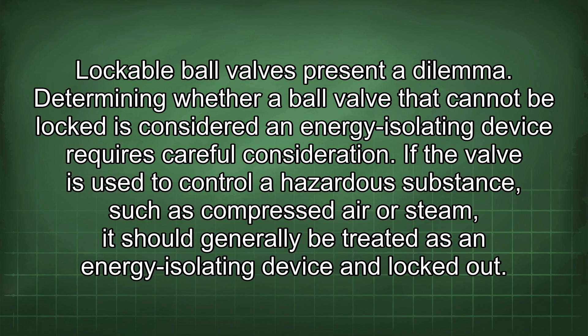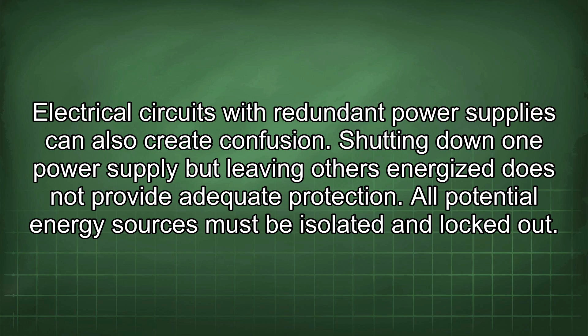Lockable ball valves present a dilemma. Determining whether a ball valve that cannot be locked is considered an energy-isolating device requires careful consideration. If the valve is used to control a hazardous substance, such as compressed air or steam, it should generally be treated as an energy-isolating device and locked out. Electrical circuits with redundant power supplies can also create confusion. Shutting down one power supply but leaving others energized does not provide adequate protection. All potential energy sources must be isolated and locked out.